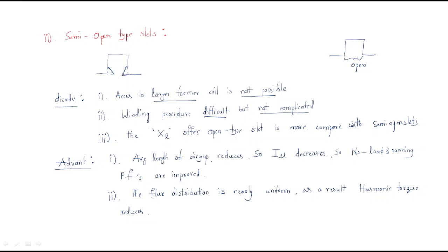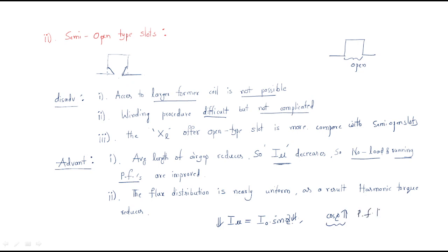First advantage: the average length of the air gap is reduced compared with the open type slot where air gap length is high. The overall average air gap length is decreased, so the magnetizing current value decreases. Magnetizing current is I-naught sine-phi; when this value decreases, sine-phi decreases, cos-phi increases, and the power factor improves. So no-load and running power factors are improved.